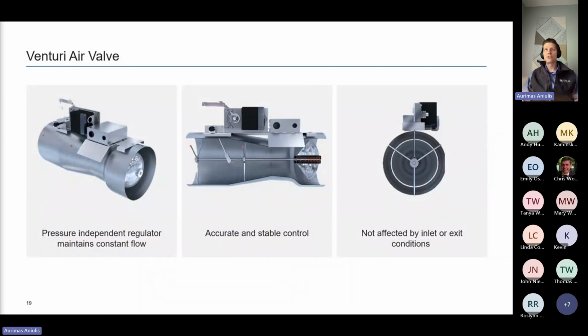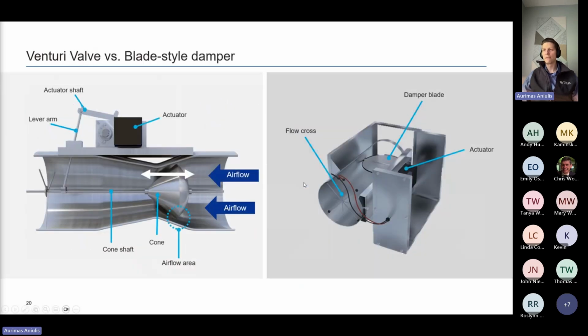So when we look at Venturi air valve technology, again, this is a 50-year-old technology. It's been around long enough where this has become a commodity in a way, and the differentiator becomes the controls that come with the valve and tying the solution together as a whole. The key value proposition of the Venturi air valve is its mechanical cone spring design with this elegant Venturi shape of the shell or the body of the valve.